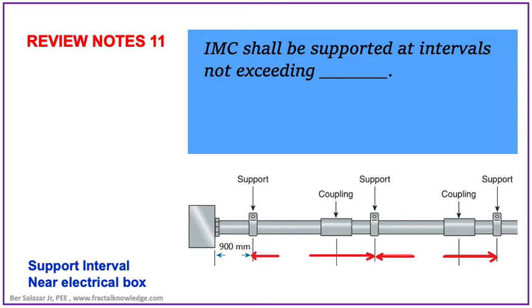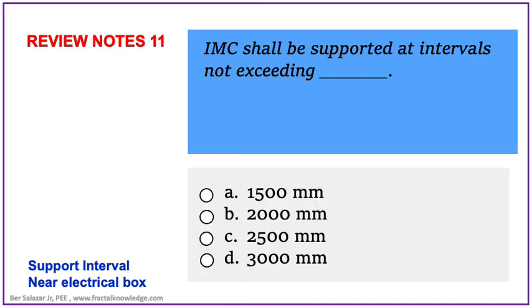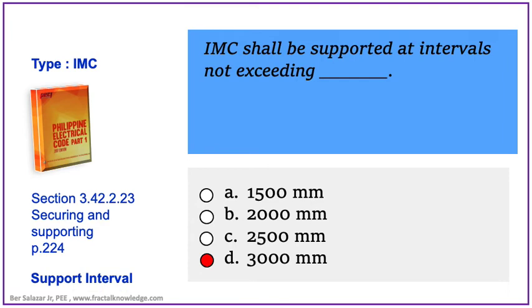The next problem asks: IMC shall be supported at an interval of how many meters? Drawings are presented for visualization but during board exam they are not there. The choices are 1.5 meters, 2 meters, 2.5 meters, or 3 meters. Based on the choices one might choose letter A, but reading PEC 3.42.2.23 paragraph B, the correct answer is letter D: 3 meters for horizontal support. For vertical support interval, the 3-meter support becomes 6 meters, provided the ends of the IMC are all threaded coupling.